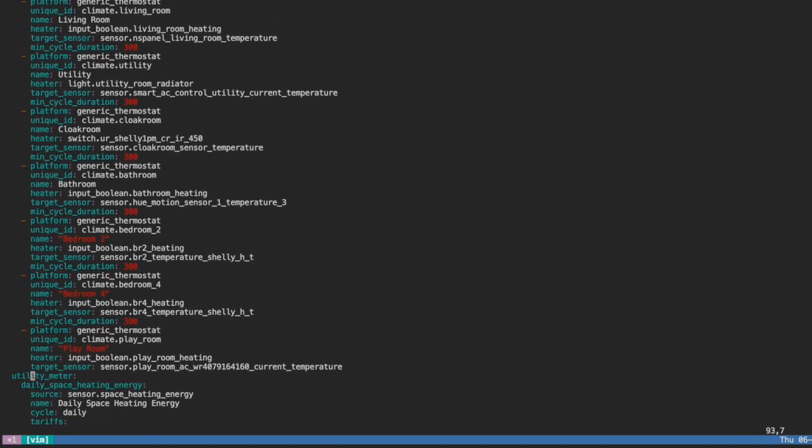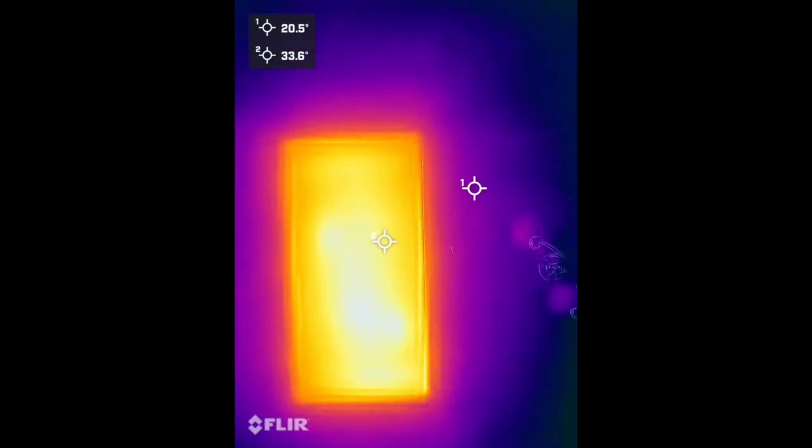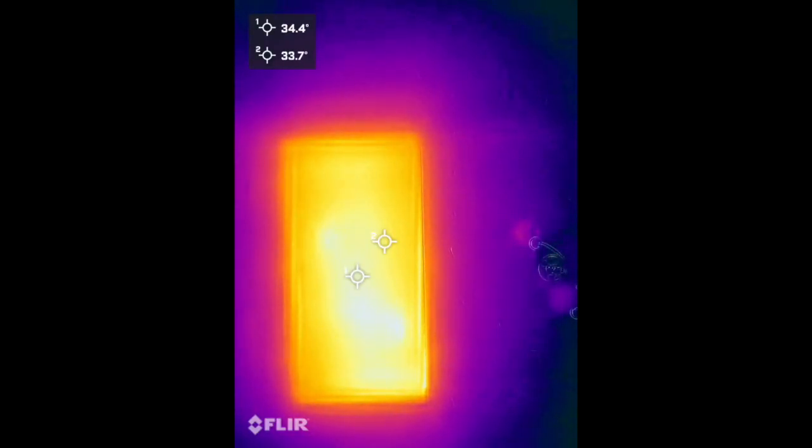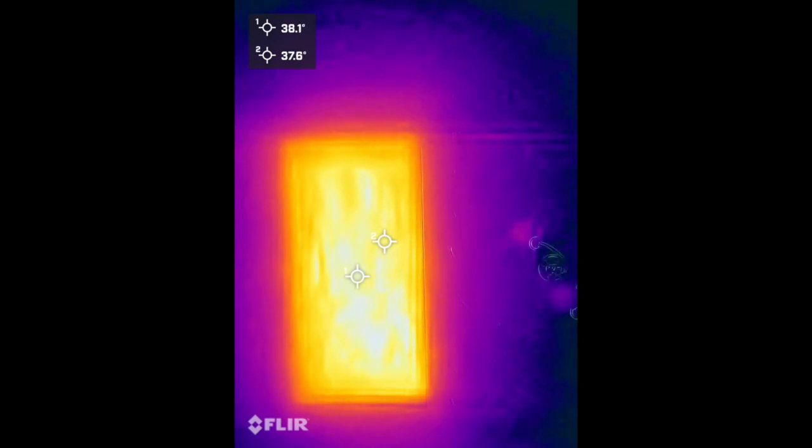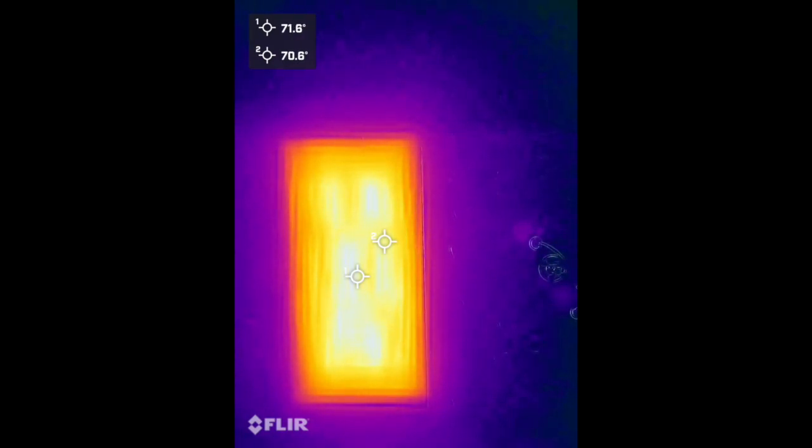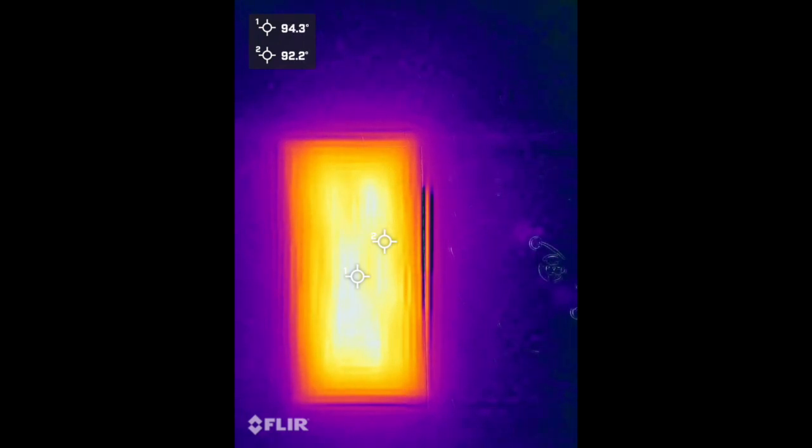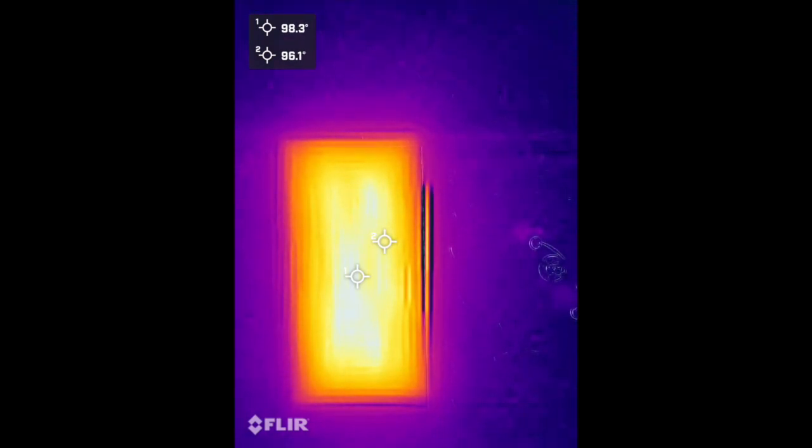Infrared emissivity of the panels is affected by their running temperature. Specifically, higher surface temperatures lead to a higher percentage of heat transfer as infrared. To ensure we are benefitting from infrared heating of the building fabric, rather than simply heating the air by convection, we are wanting to ensure that run times are long enough to enable the panels to reach this optimum temperature. It's too late this year to see what difference this makes, but come autumn we'll see how valuable these changes are.